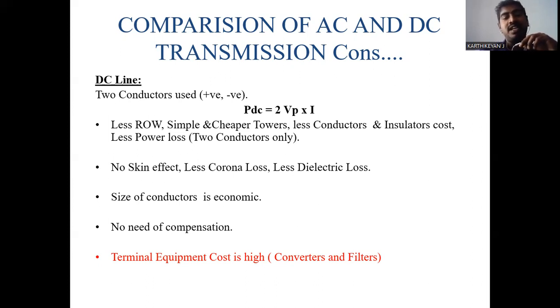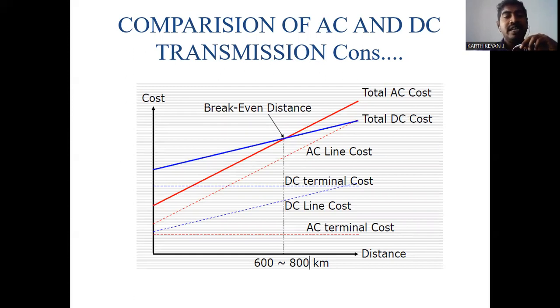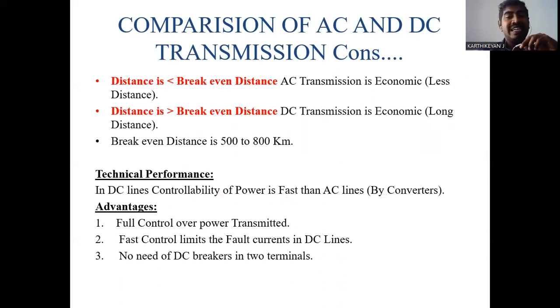There is no need for compensation devices in a DC transmission line, which is an advantage over AC. However, DC equipment cost is higher than AC. An AC line uses three conductors of the same size, while a DC line uses only two conductors. From the cost comparison graph, the total AC cost is higher than the DC transmission system for long distances. When the distance is less than the break-even distance, AC is more economical; beyond the break-even distance, DC is more economical.